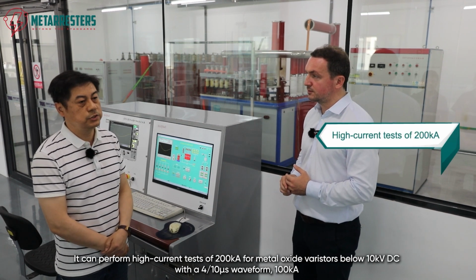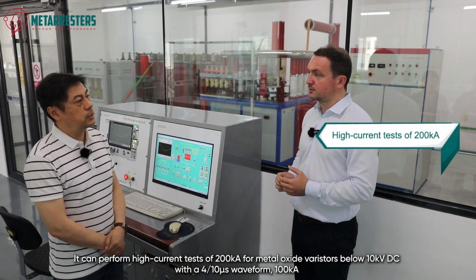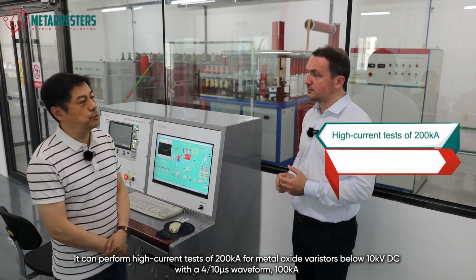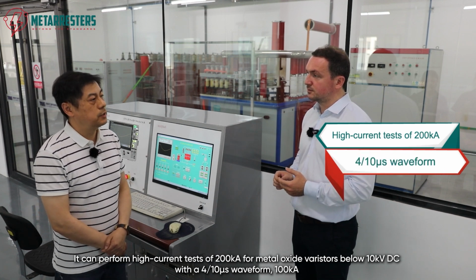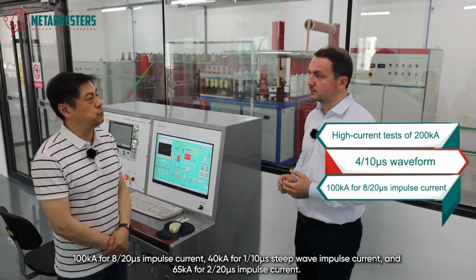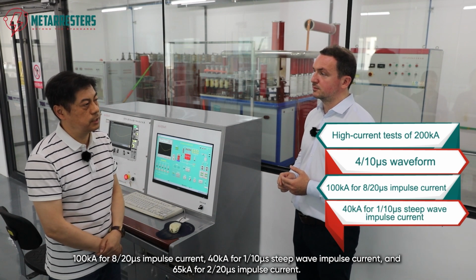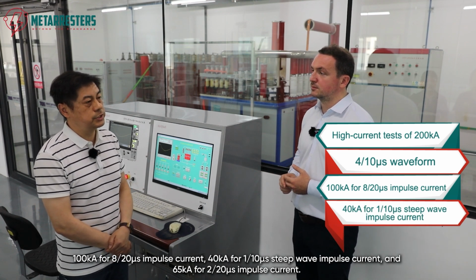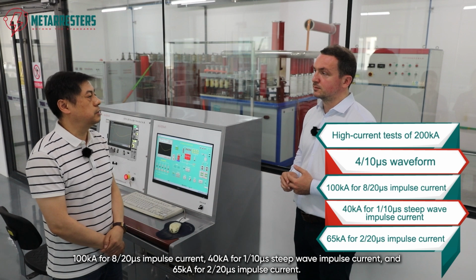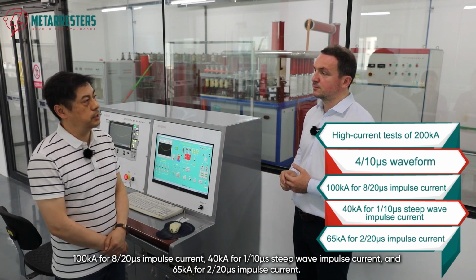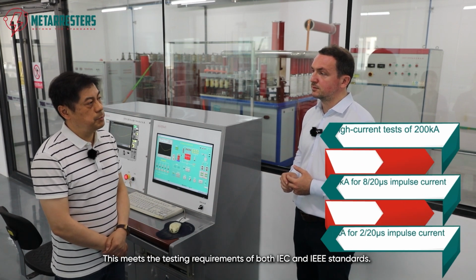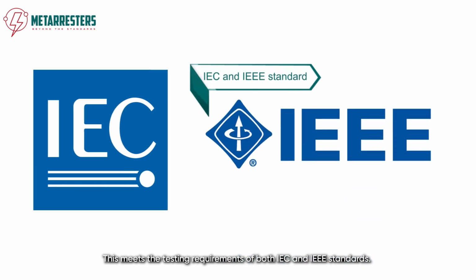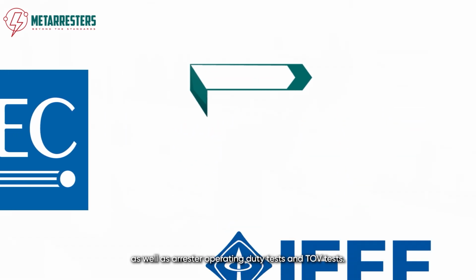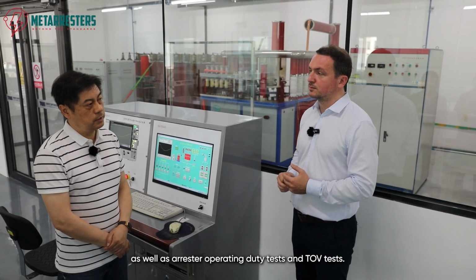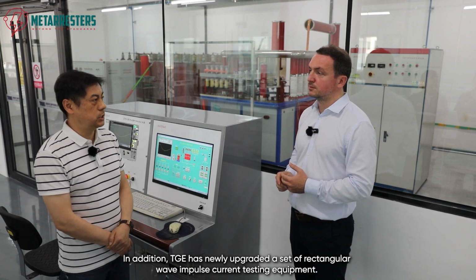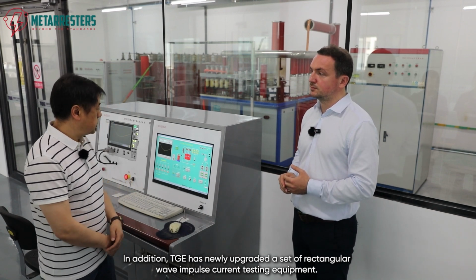It can perform high current tests of 200 kiloamperes for Metal Oxide Varistors below 10 kilovolts DC with a 4/10 microsecond waveform, 100 kiloamperes for 8/20 microseconds impulse current, 40 kiloamperes for 1/10 microseconds steep wave impulse current, 65 kiloamperes for 2/20 microseconds impulse current. This meets the testing requirements of both IEC and IEEE standards, as well as arrestor operating duty tests and TOV tests. In addition, TGE has newly upgraded a set of rectangular wave impulse current testing equipment.